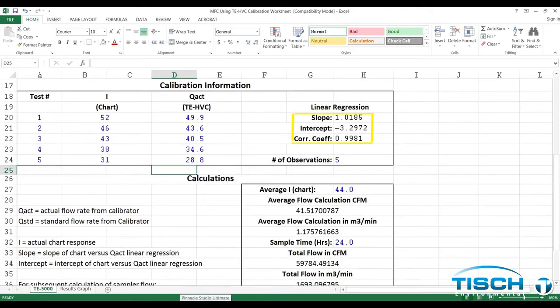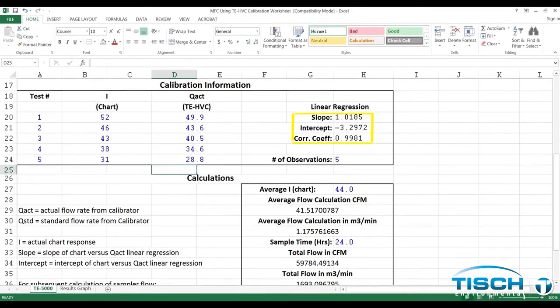Our slope is 1.0185 and the intercept is negative 3.2972. Our correlation coefficient is 0.9981, which is a good calibration. Anything under 0.990 is a bad calibration.